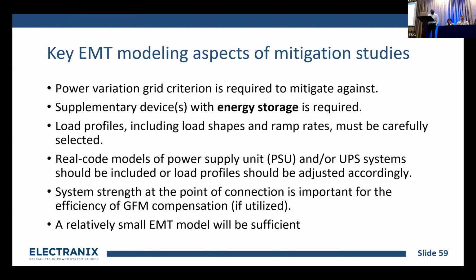And a relatively small EMT model is required, so you don't need a big wide area PSCAD model to do these studies. Pretty much like a model quality test, MQT testing, like a SMIB model. You can use that kind of model for the mitigation studies. And the system strength is important. What are the SCR and X/R values that you use? Because that will have an impact based on the type of mitigation method you use. If you use GFM batteries, the grid strength matters because your initial phase jump power depends on how much grid strength there is.